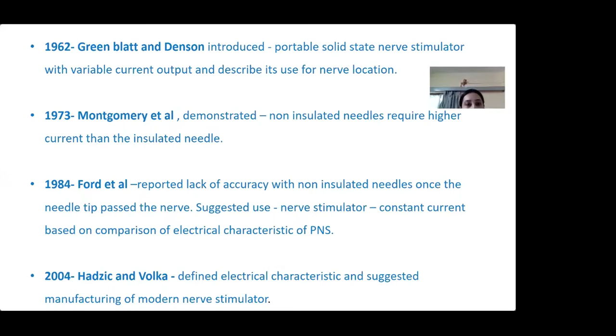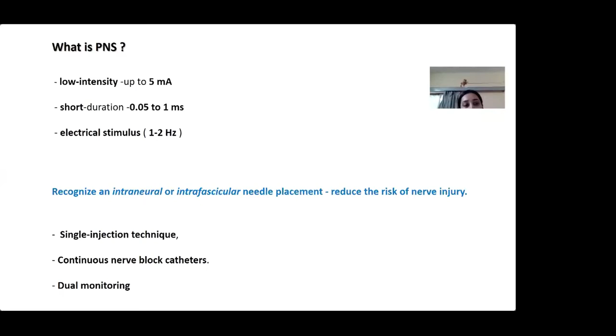What is peripheral nerve stimulator? It is a method of using low intensity current up to 5 milliampere with a short duration pulse width of 0.05 to 1 millisecond and an electrical stimulus frequency of 1 to 2 Hz. It helps in recognizing an intraneural or intrafascicular needle placement and prevents its further advancement and reduces the risk of nerve injury. It can be used as a single injection technique, continuous nerve block for the insertion of the continuous nerve block catheters, and also as a part of dual monitoring, that is the use of ultrasound along with the peripheral nerve stimulator. And it has become a basis for the medico-legal aspect.